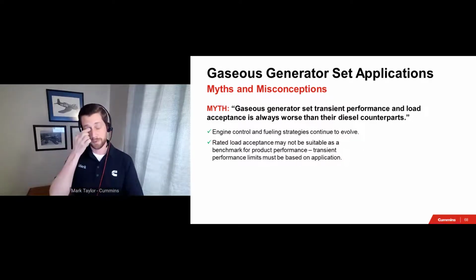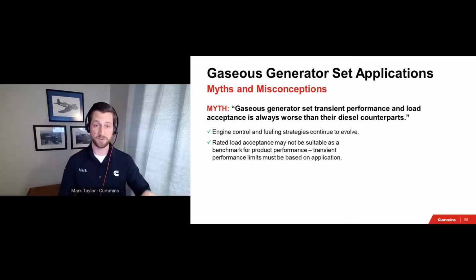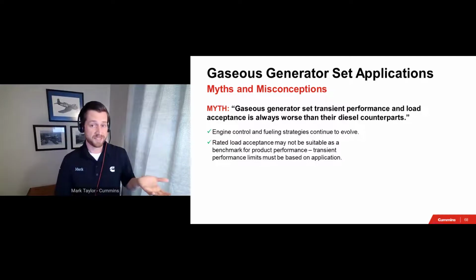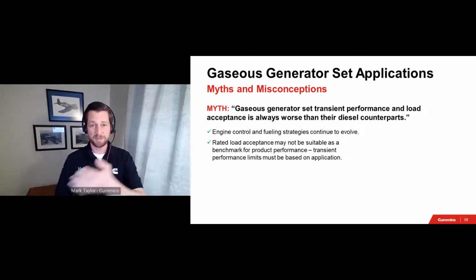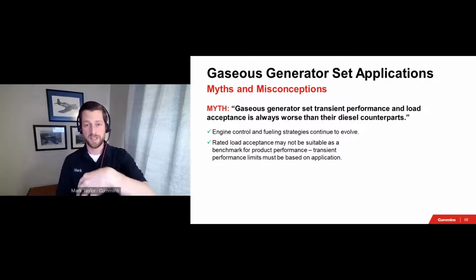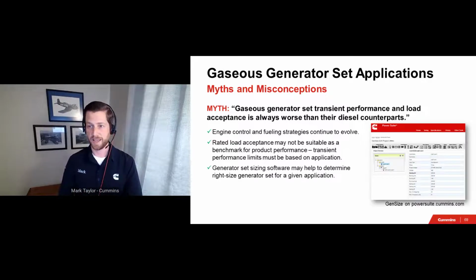Further, this is a great opportunity to highlight that performance against 100% rated load acceptance may be an interesting basis of comparison on paper, but not nearly as practical a comparison between products as the actual required load performance of that application. The best way to evaluate how a generator set may perform against the loads and load sequencing in your design is to run it against the product sizing software. I also challenge you to evaluate both diesel and gaseous fueled options, not ruling out one from the onset. If you have any notions that diesel is always better than gaseous fueled generator sets, I'm sure you'll be delightfully surprised to see how capable they are if you give them a shot.